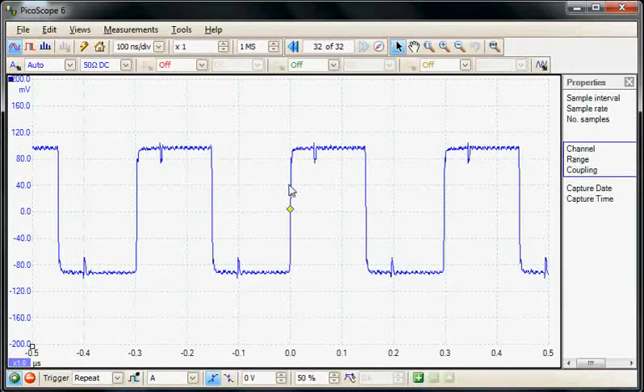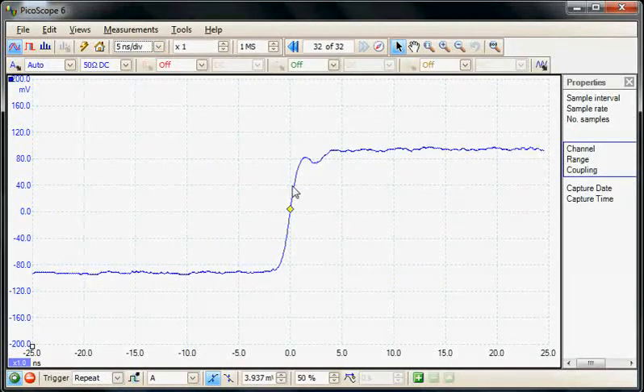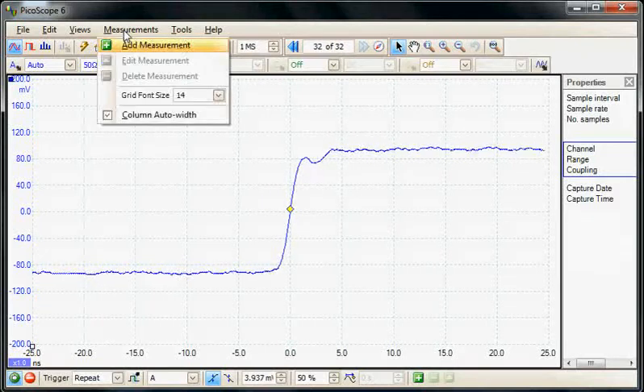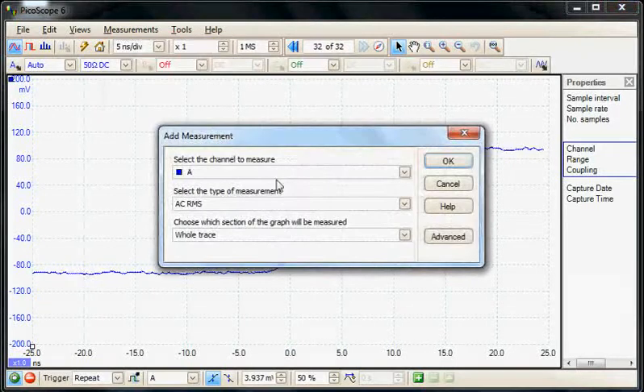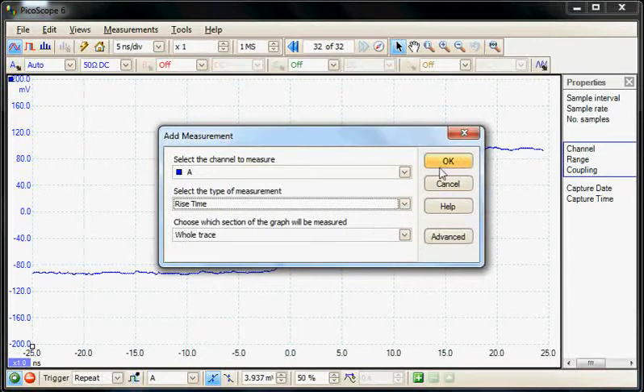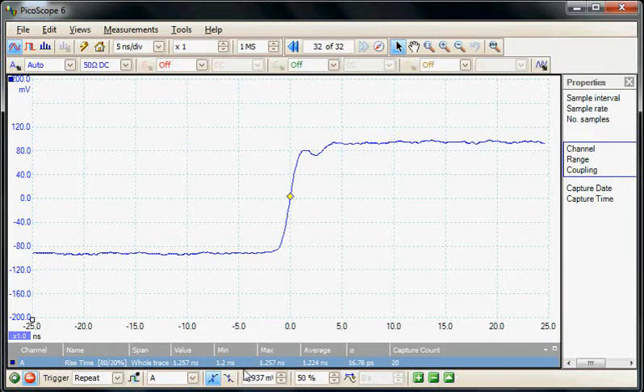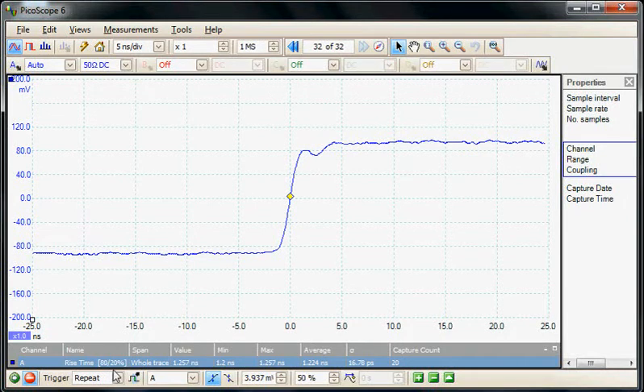I'm going to increase the time base and measure the rise time on this edge, going to a faster time base speed. I'll add a rise time measurement from channel A and leave it on the whole trace. Stopping the acquisition, we can see the rise time measurement is 1.2 nanoseconds — and this is a 20 to 80 percent measurement.